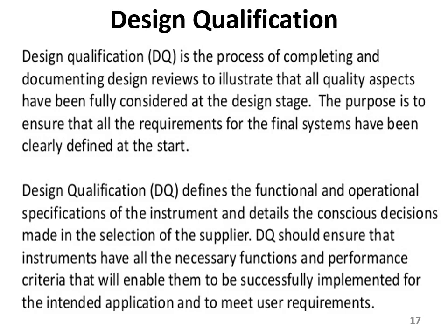So DQ, or design qualification, is actually the functional and the operational specifications of the instrument and details regarding the conscious decisions made in the selection of the supplier. You should ensure that the instrument has all the necessary functions and the criteria that are going to enable you and the machine to successfully go through the system and implement all the requirements and the needs of the user.